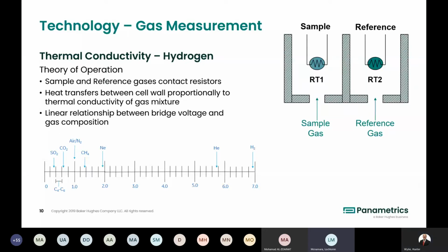Yeah, well, in terms of the XMO2 and XMTC, yes, they're binary gas analyzers. We need to measure, say, oxygen in a known background gas, but we do have the ability to compensate for other gases within it, and it's the same with the XMTC. We call it a pseudo-binary gas because we can calculate or compensate for certain gas changes within the background. So the error might be a little bit bigger, but it's still insignificant in terms of the overall measurement that's required. So certainly, yeah. I hope that answers the question.